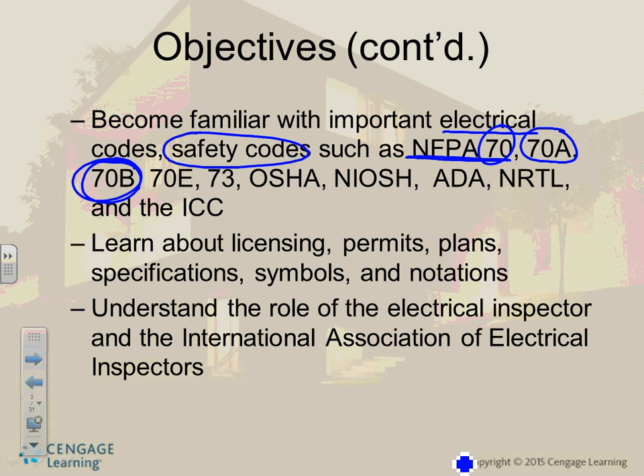70B, guys, is the maintenance code. How do you maintain an existing building? When you become a project manager after 10-15 years and get into a building, your job is to maintain the electrical equipment, you need an electrical maintenance plan. That 70B is very powerful, detailed information on how to maintain a switchgear, switchboard, panel, UPS, in detail, checklist based on manufacturer information. 70E is the safety code, directly the safety code.